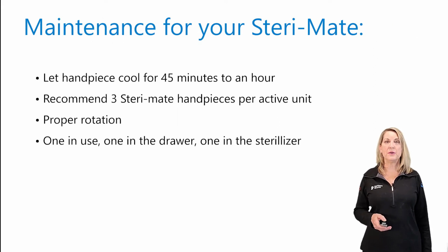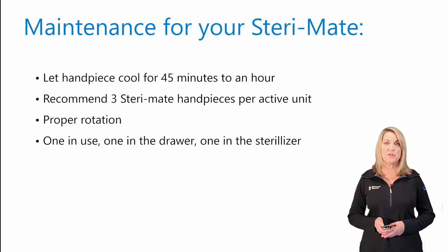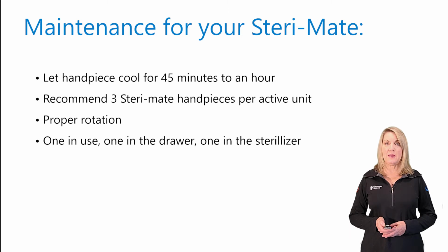After reprocessing the Steri-mates, I have found that you need to leave them cool for approximately 45 minutes to an hour to allow them to fully reach room temperature so that there is absolutely no heat left that could potentially damage or warp the Steri-mates once you run cold water through them. It is recommended that you have an average of 3 Steri-mates per active Cavitron unit in your office. This will allow you the ability to have proper rotation. Always keep in mind 1 Steri-mate will be in use, 1 in the drawer ready for use, and 1 in the sterilizer. Next, let's review some troubleshooting items.